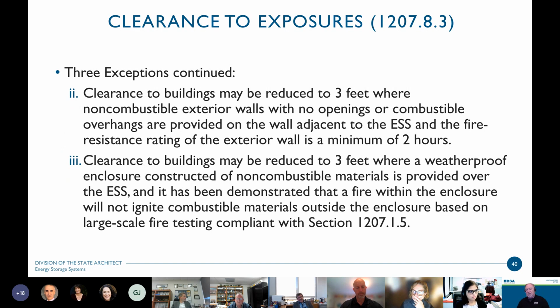Second exception, again, allows the reduction down to 3 feet where non-combustible exterior walls with no openings or combustible overhangs are provided on the wall adjacent to the energy storage system installation, and the fire resistance rating of the exterior wall is 2 hours. So if you have an existing building that has non-combustible exterior construction with no openings and a 2-hour wall, you can pop these things within 3 feet. If you don't have a building that meets this, then certainly you're going to have to look at upgrading that existing building to meet these requirements.